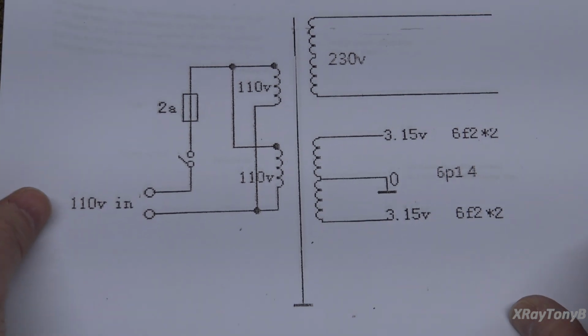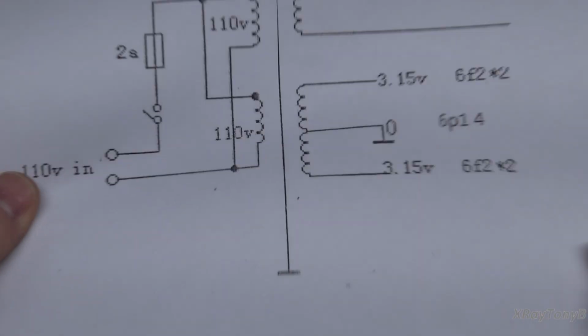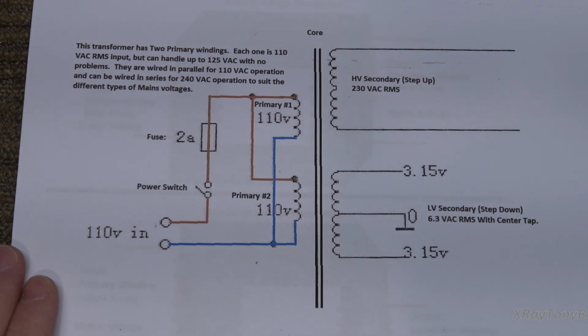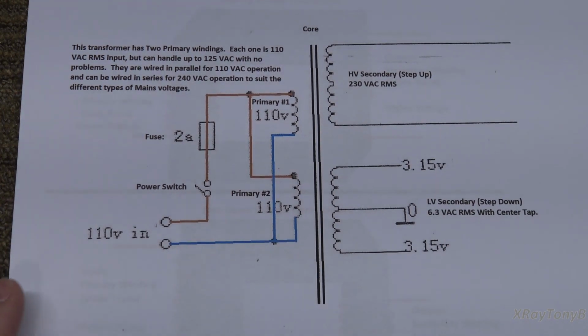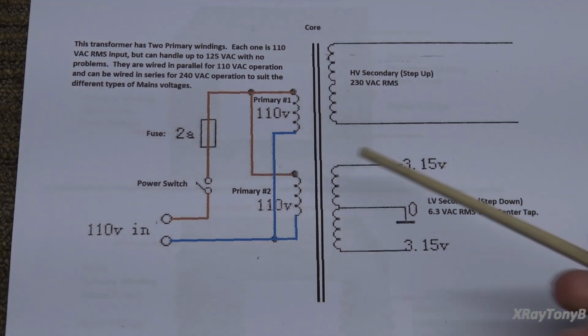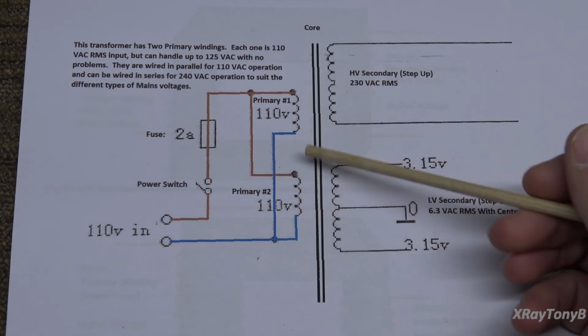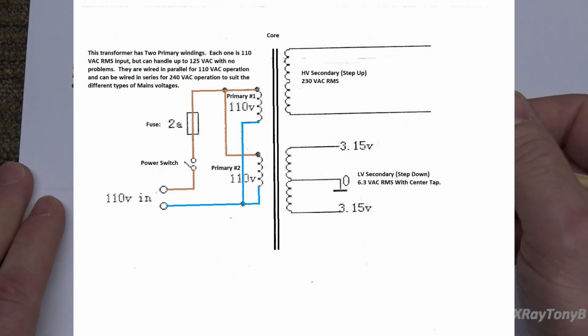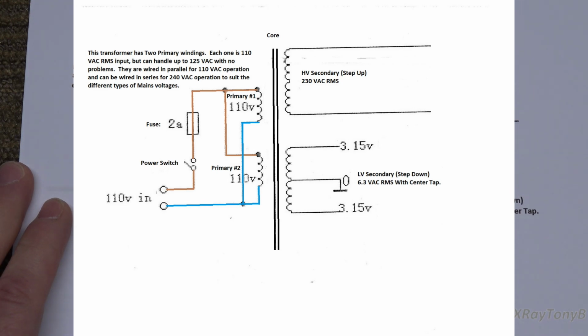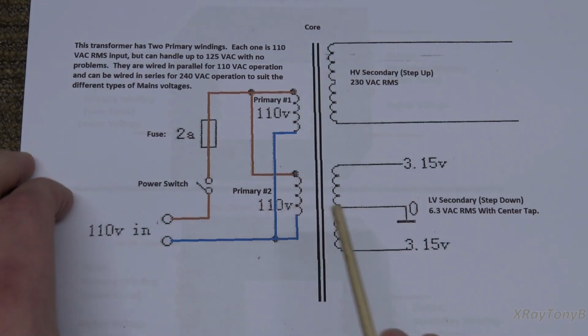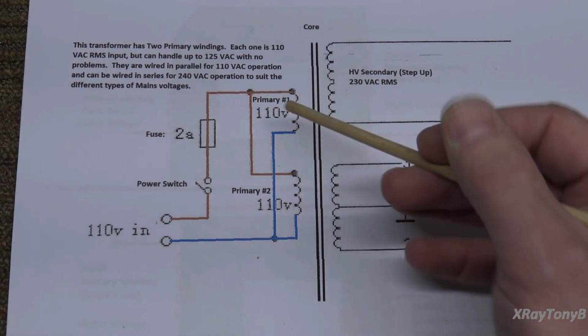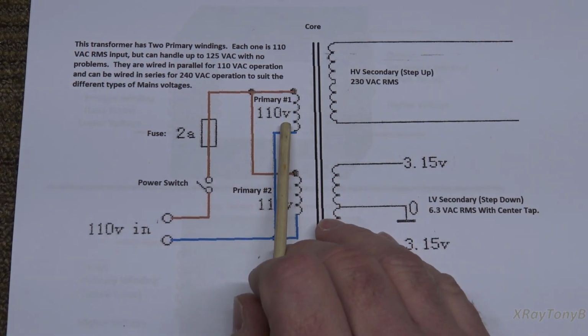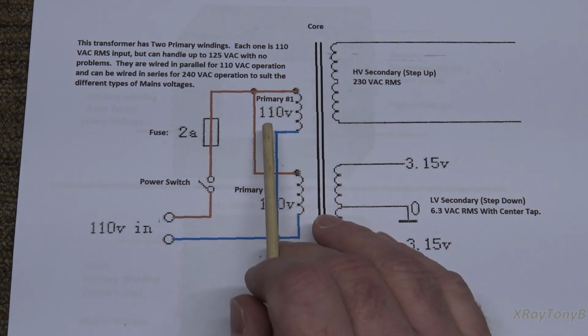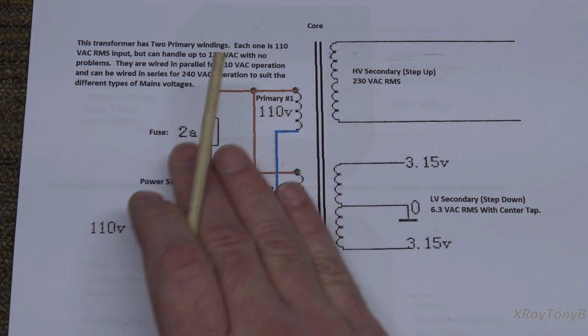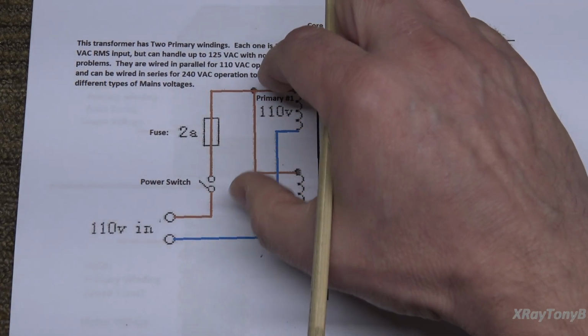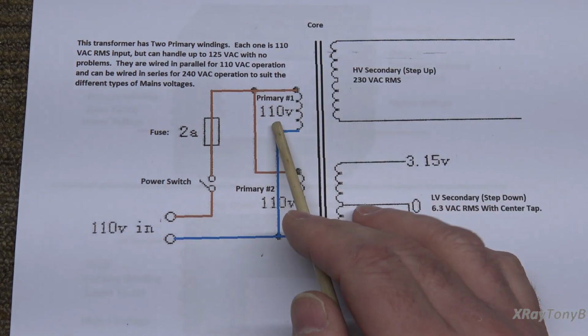Let's look at a little more detail of this. The transformer we have here has two primaries, and each one is designed to have 110 volts input, nominal. Now you can run this up to 120 volts and it won't hurt it, but the measurement point they're using takes into consideration that you're putting 110 volts in.